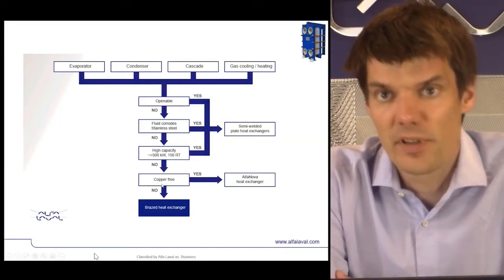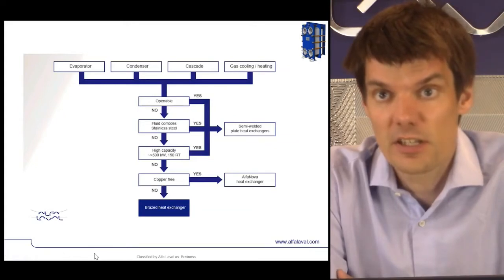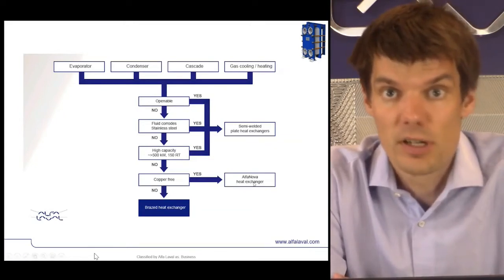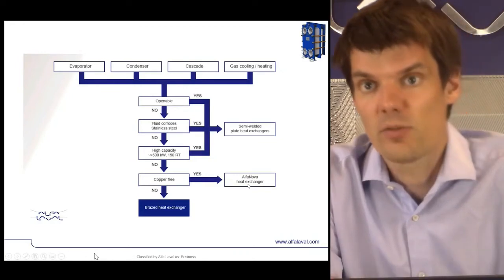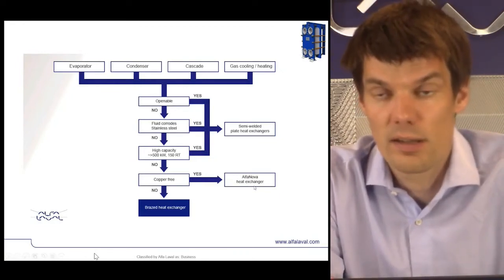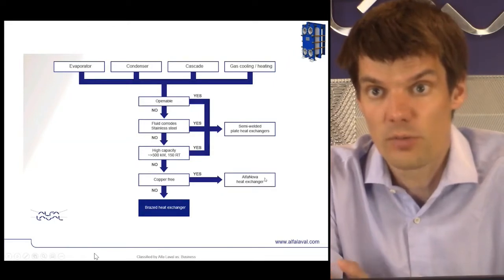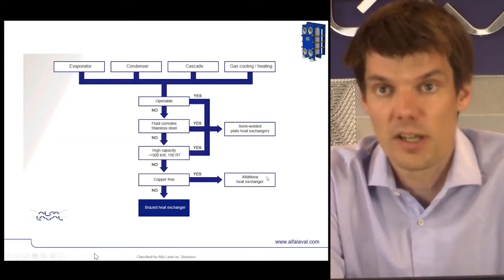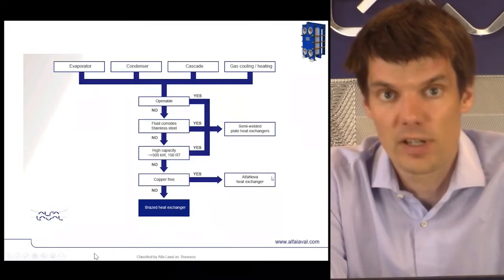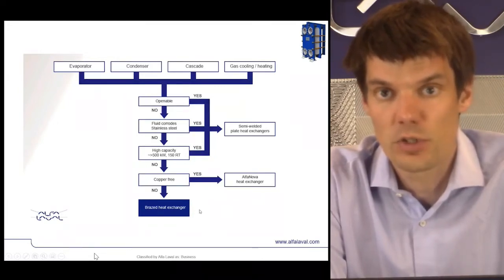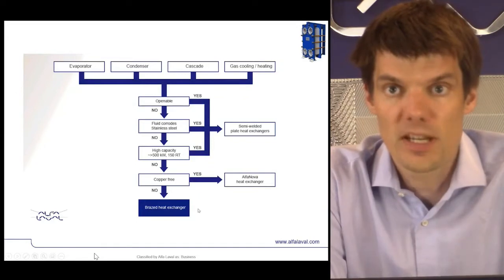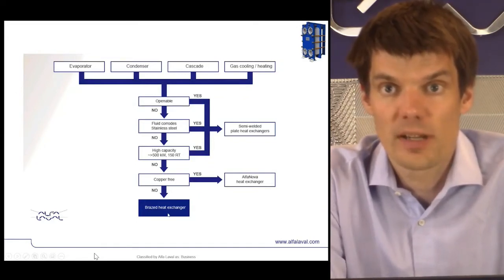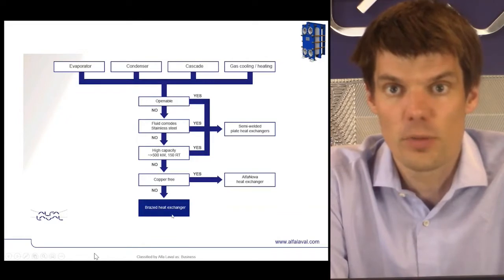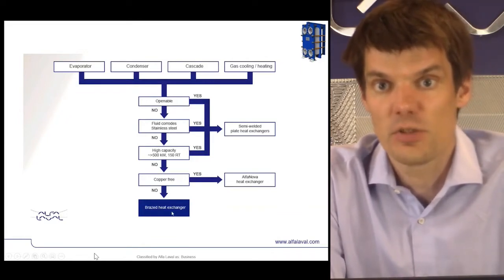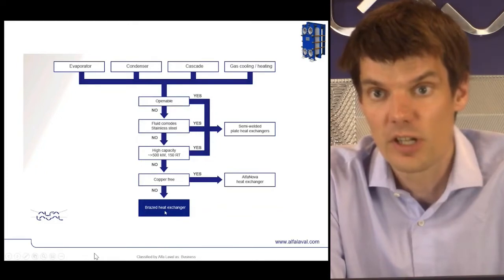If nothing of the above is applicable, one can ask if the heat exchanger needs to be copper free. If that's the case, for instance, we are operating with ammonia, or we would need to operate with, for instance, tap water application, then we will recommend the Alfa Nova, the 100% stainless steel fusion bonded plate heat exchanger. Coming that far, for everything else, we would recommend a brazed plate heat exchanger due to the thermal performance and the fact that this heat exchanger is using the majority of material for heat transfer and therefore being the most affordable solution.